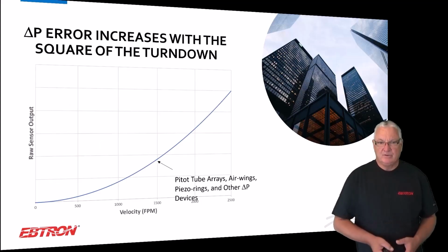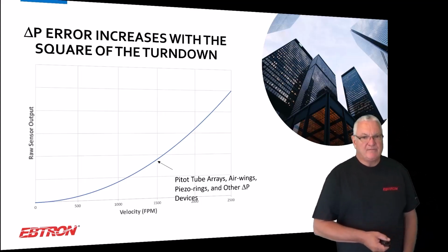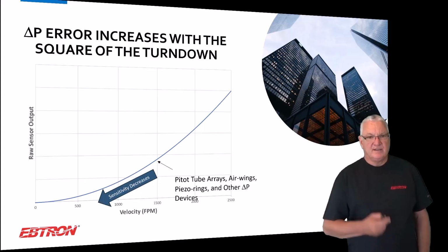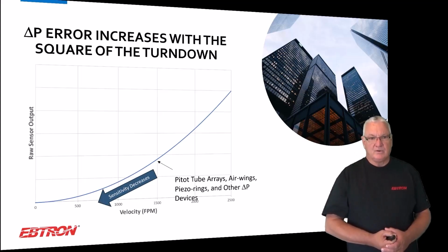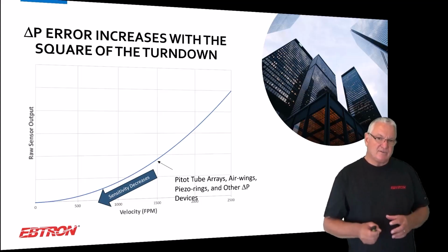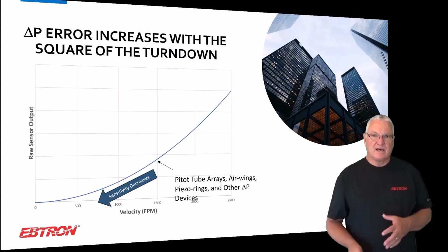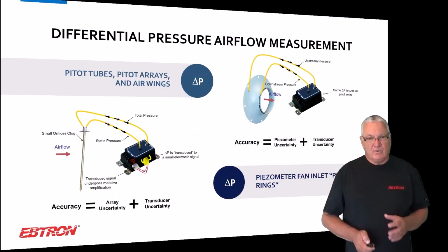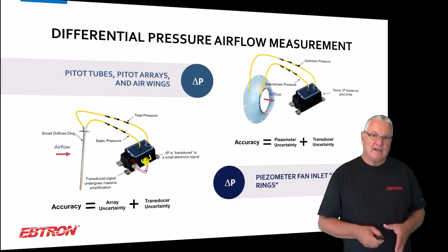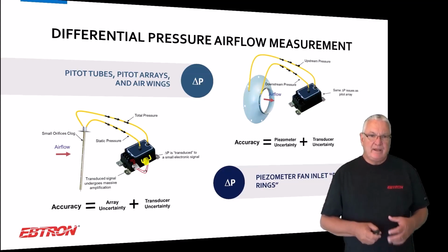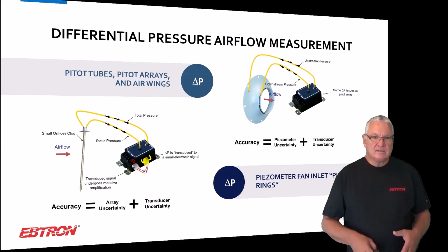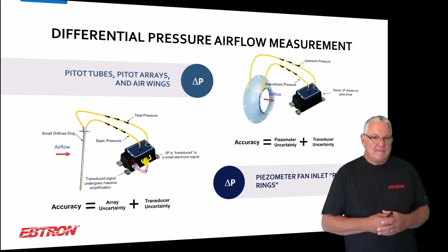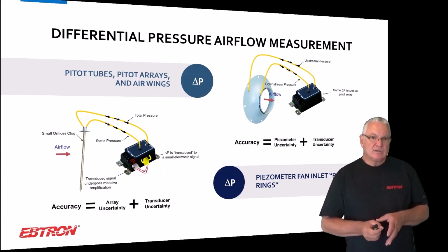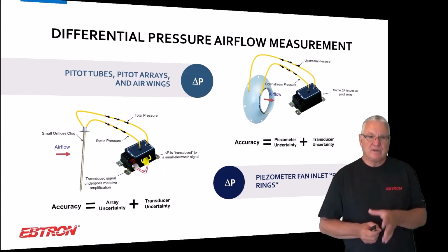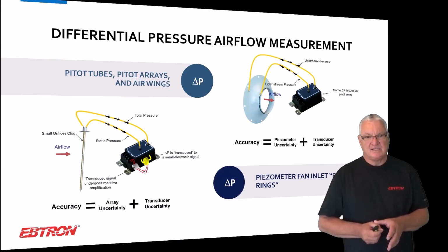When you compare that to pitot tube arrays or air wings, which are really pitot tube arrays, piezo rings, and other delta P devices, you have pretty much a square root relationship where the sensitivity decreases with flow. So that makes those devices not really good choices typically when you have lower flows or a lot of turn down. Okay, so when you look at these devices, what am I talking about? What are DP devices? Well, pitot tubes, pitot arrays, air wings, they're basically devices that will average the velocity pressure, and then that velocity pressure goes to a single pressure transducer that will then convert that velocity pressure to flow.